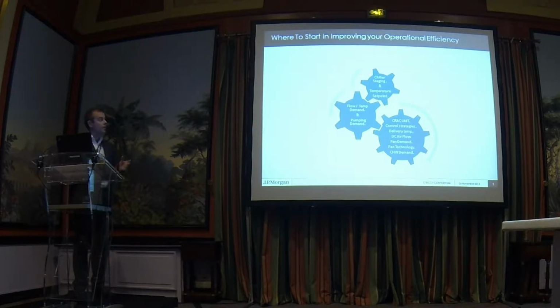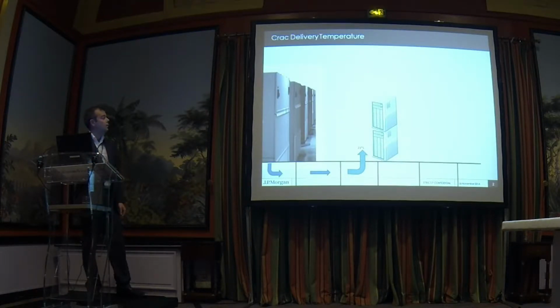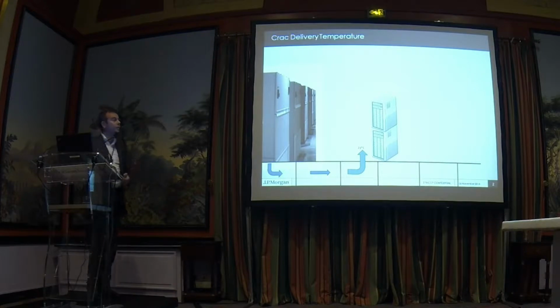So the servers, IT infrastructure, is process cooling. Air goes in, air goes out. The server doesn't complain if it gets 10 degrees or 26 degrees. So the air delivered in the majority of our data centers now is at 21 degrees C. We're looking to bring that up to around 25. I believe most server manufacturers get to about 26, 27, and the fans start ramping up in the machine. So it makes your PUE look better, but you're just burning more power for no reason.